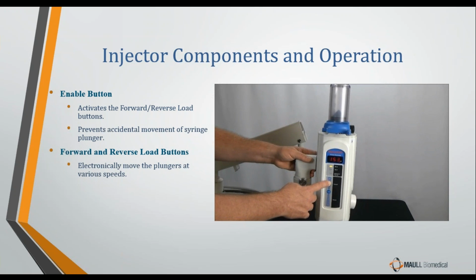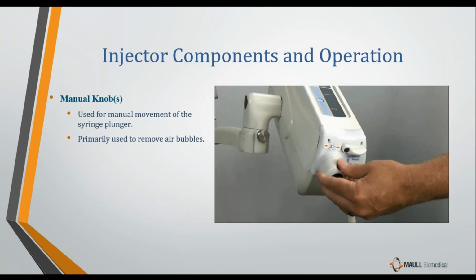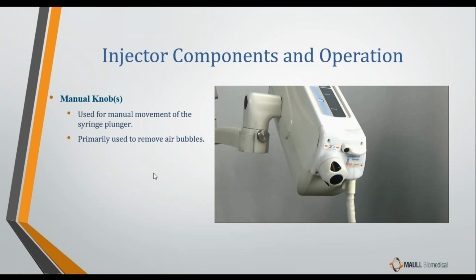Now, most contrast injectors have variable speed load buttons: slow, medium, and fast forward, and slow, medium, and fast reverse as well. The primary function, really the only function, of the manual knob is to manually prime the syringe and the connector tubing of any air. Once the syringe has been filled up, they'll typically use the manual knob to get out any air bubbles or air left in the syringe or connector tubing before hooking it up to the patient. That's really the only purpose of the manual knobs.